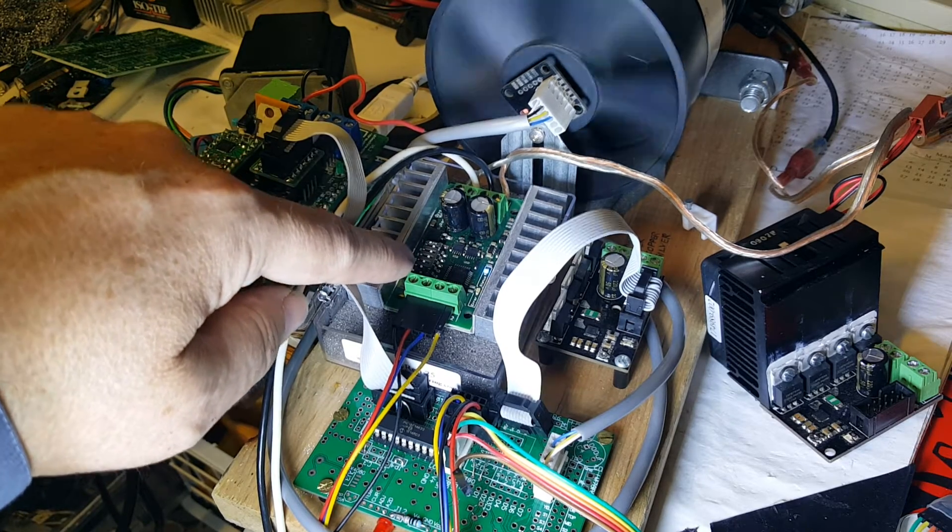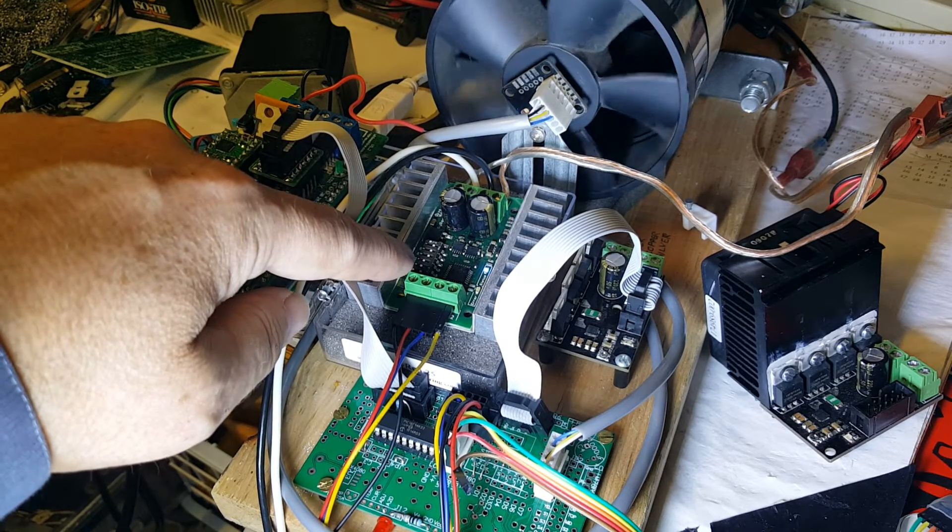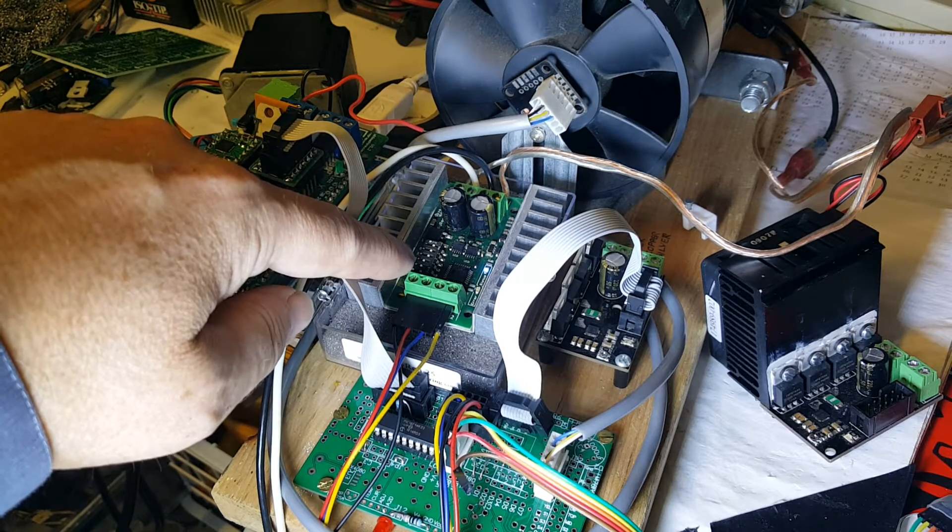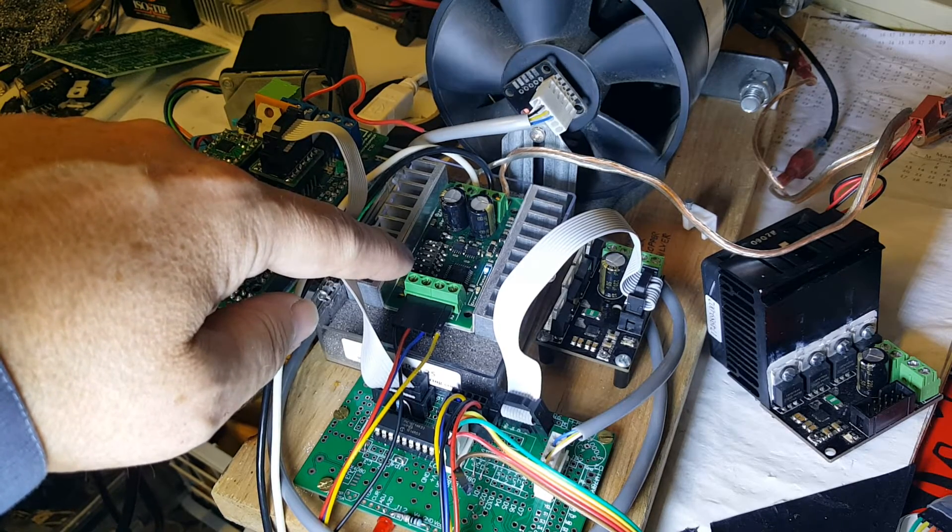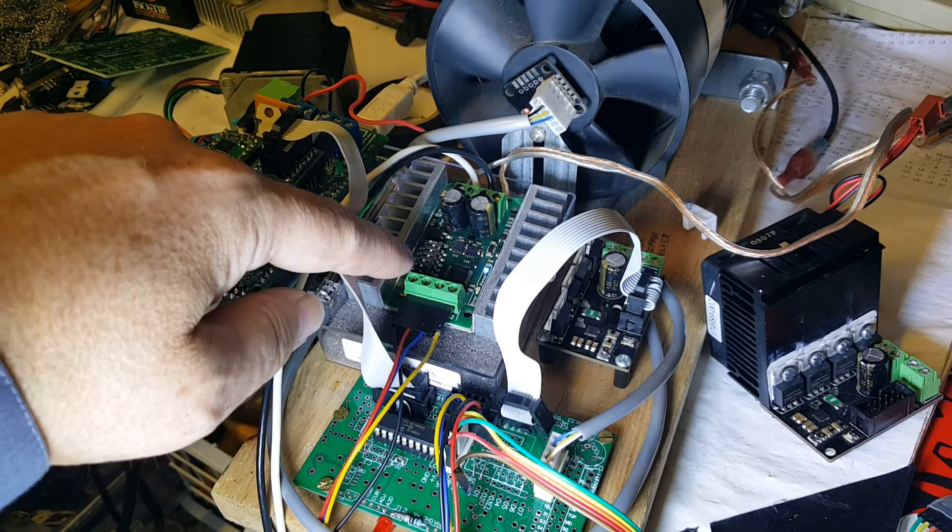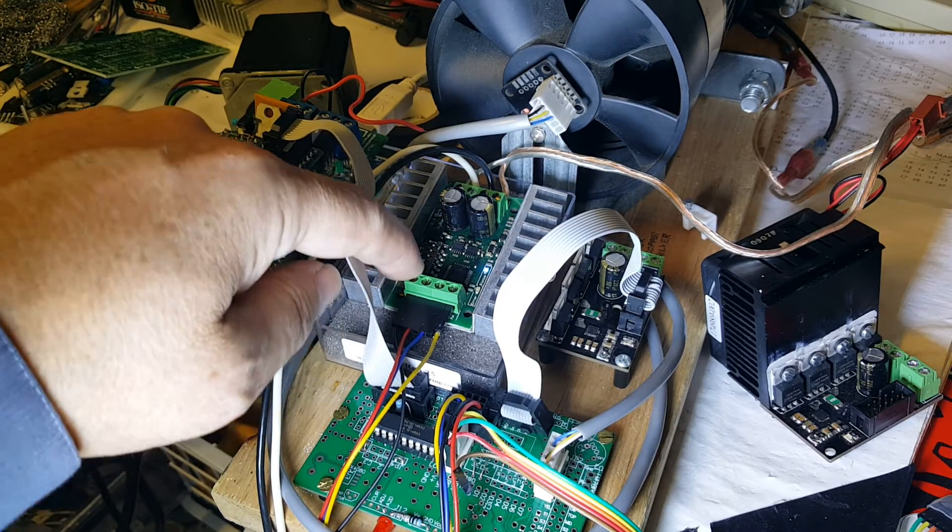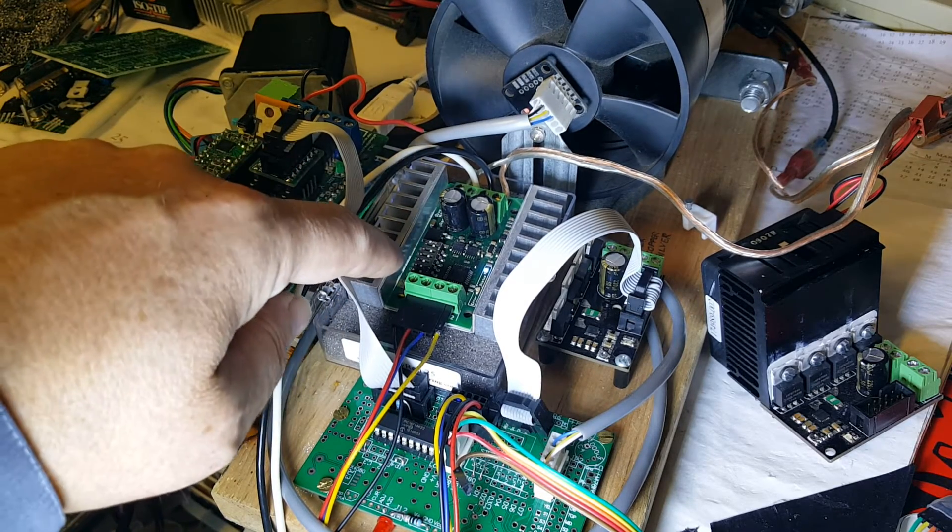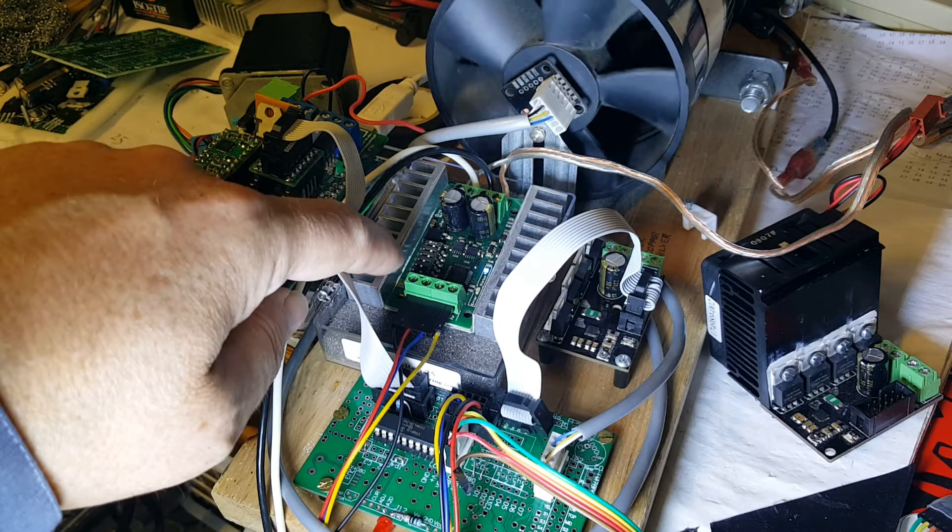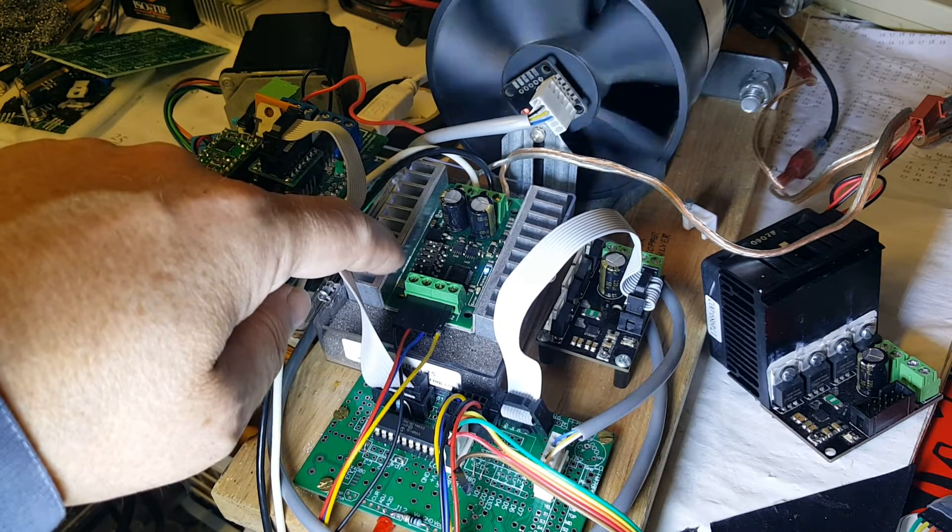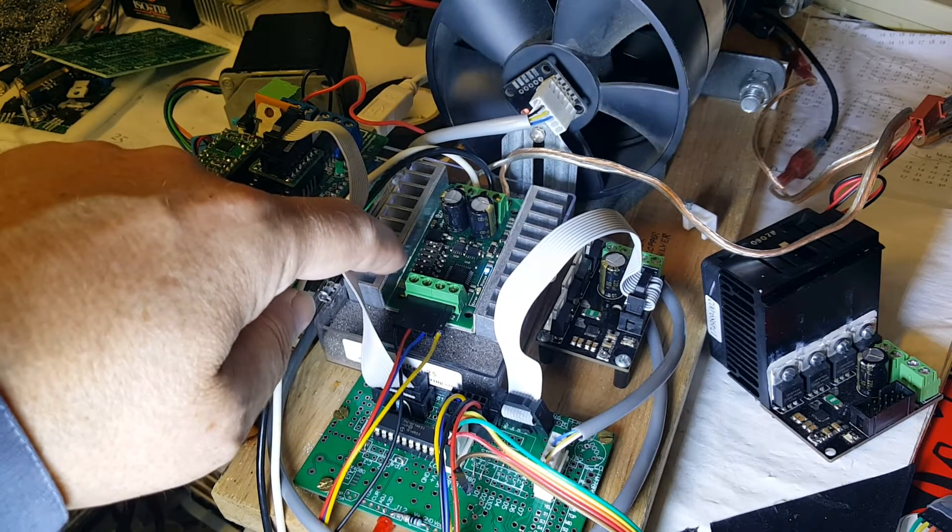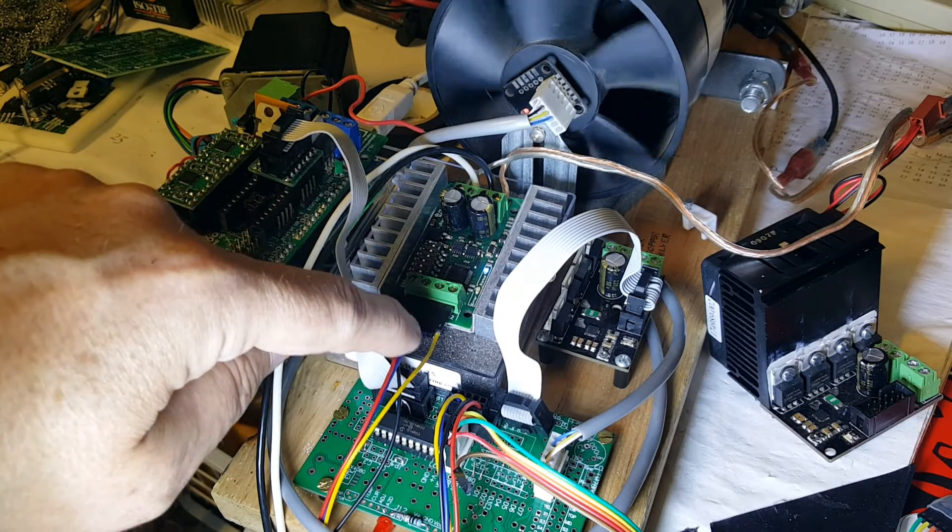It's called option 3: Analog 1 Direction with Forward Reverse Select on S2. You set the mode switches here to 1-2-3 on, 4-5 off, and then 6 on.